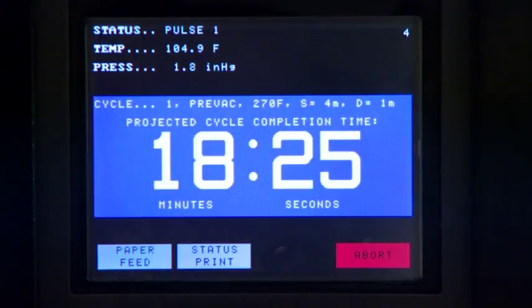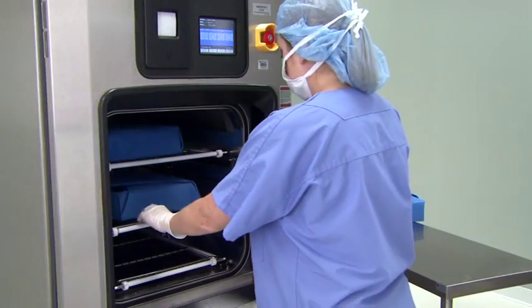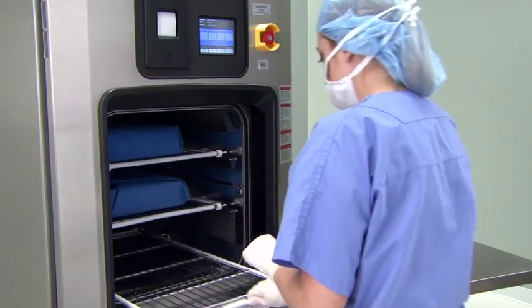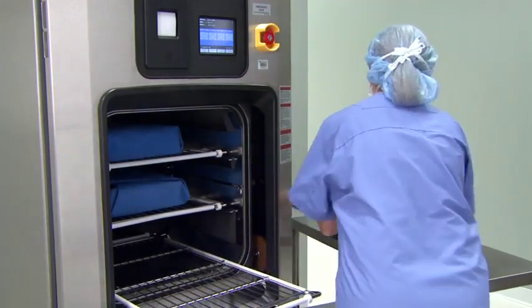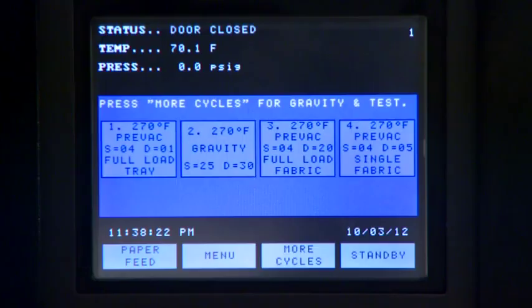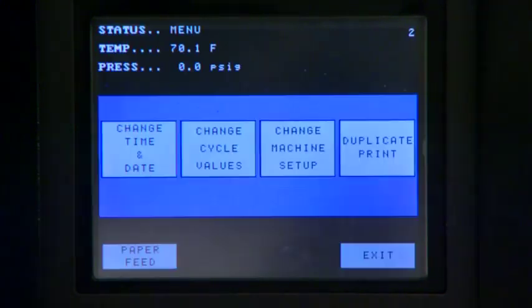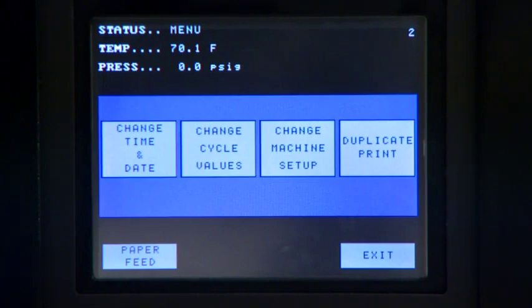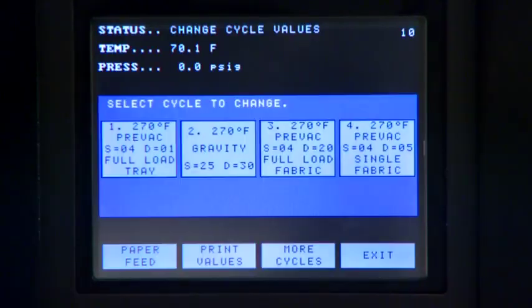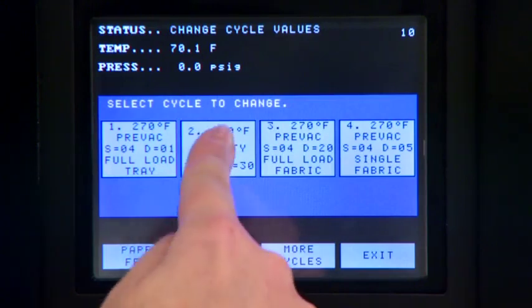If cycle parameters, sterilize time, dry time, or temperature other than the factory set values are required, it is the responsibility of the healthcare facility to consult and follow the device manufacturer's written instructions for processing. To adjust the sterilizer's operation, press the menu button. The Change Time and Date, Change Cycle Values, Change Machine Setup, and Duplicate Print buttons are displayed. To change cycle values, press the Change Cycle Values button. Then press the cycle button number you want to change.